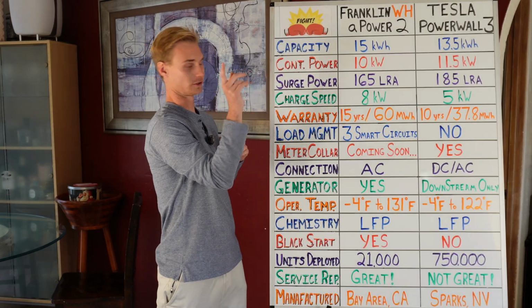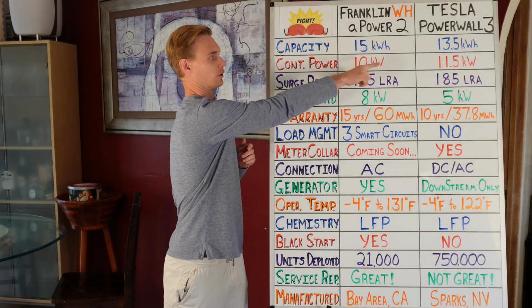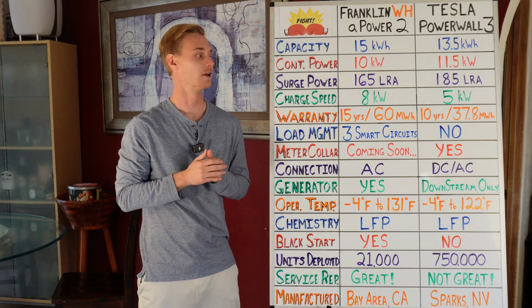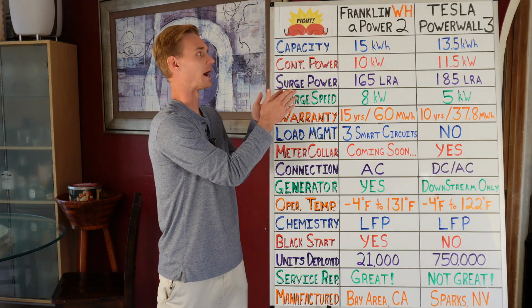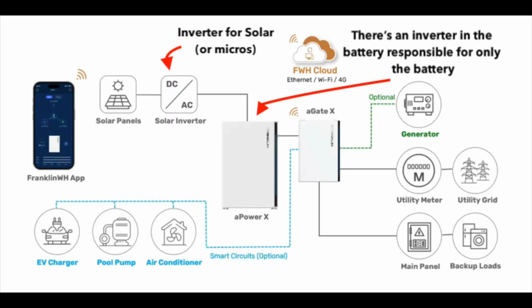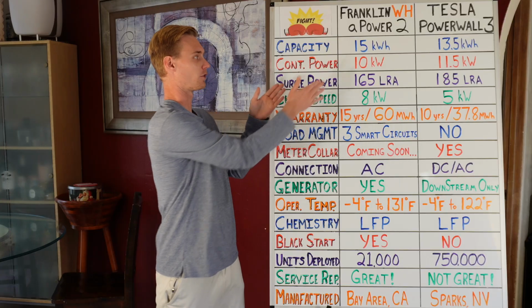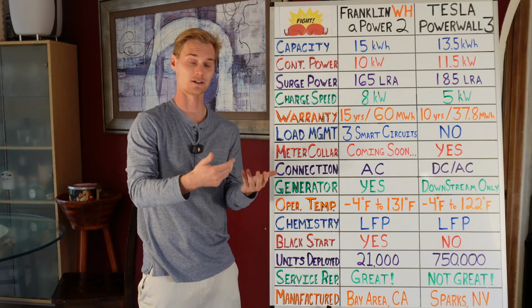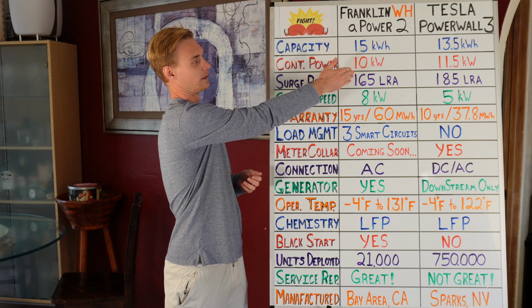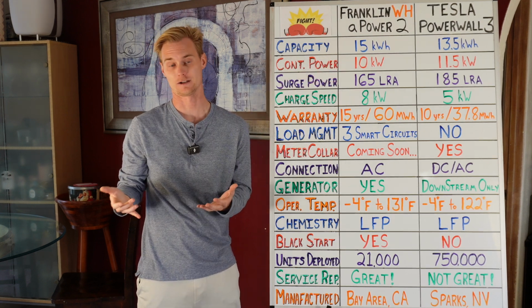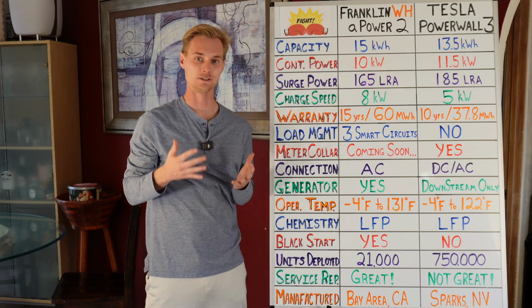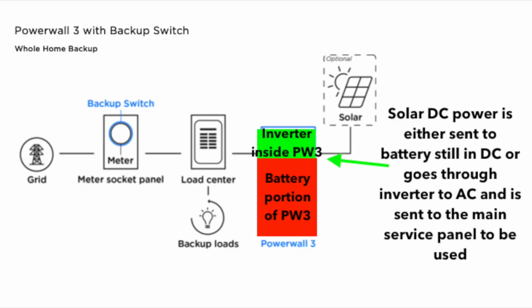One thing to consider when looking at this 10 kilowatt versus 11.5 kilowatt continuous power output is that Franklin is an AC coupled battery. That means the power from the inverter in the battery, 10 kilowatts, can be combined with the solar's inverters. For example, if you're using microinverters, all the kilowatts from the solar and the battery can be combined, so in the daytime you could actually have far more than 10 kilowatts of continuous power if needed - versus the Powerwall 3, which is a DC coupled architecture that uses a hybrid inverter.